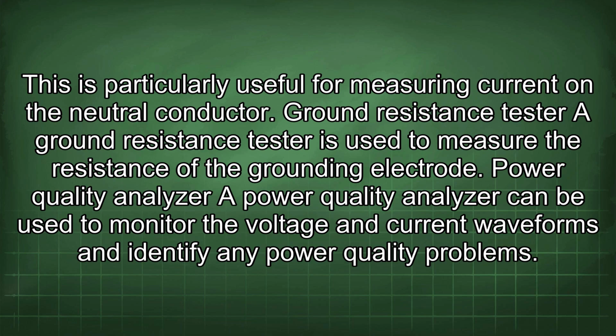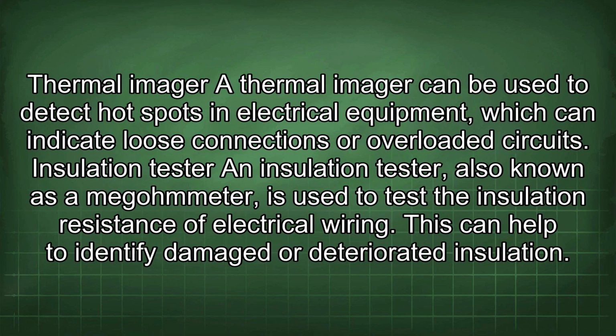power quality problems. Thermal imager. A thermal imager can be used to detect hot spots in electrical equipment, which can indicate loose connections or overloaded circuits. Insulation tester. An insulation tester, also known as a megohmmeter, is used to test the insulation resistance of electrical wiring. This can help to identify damaged or deteriorated insulation.